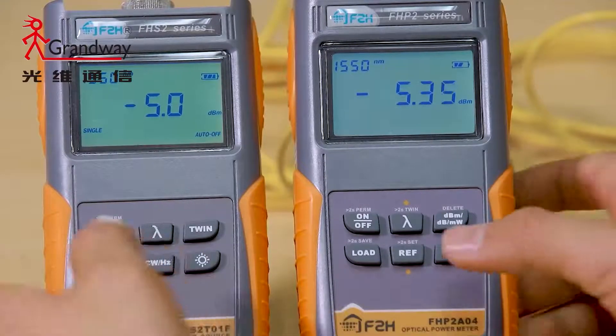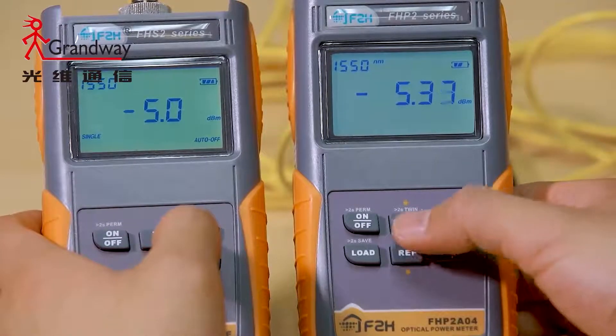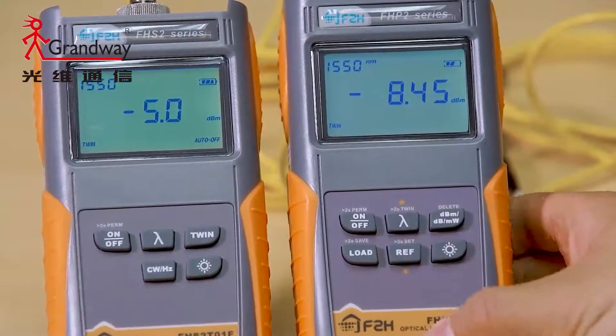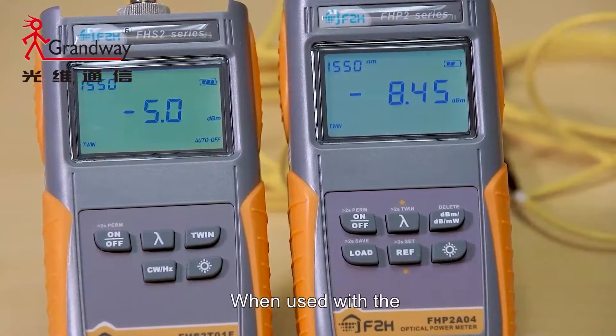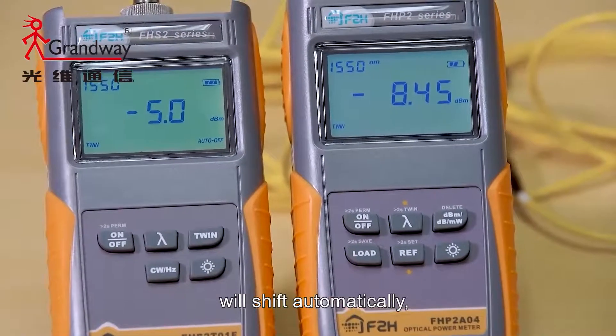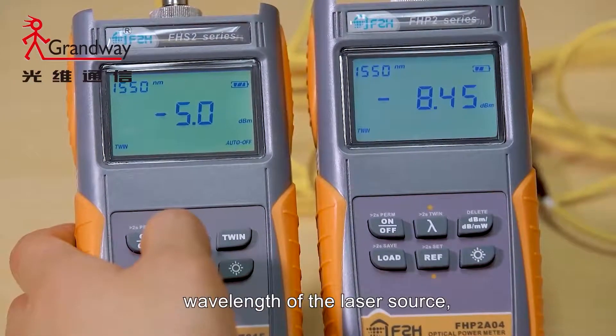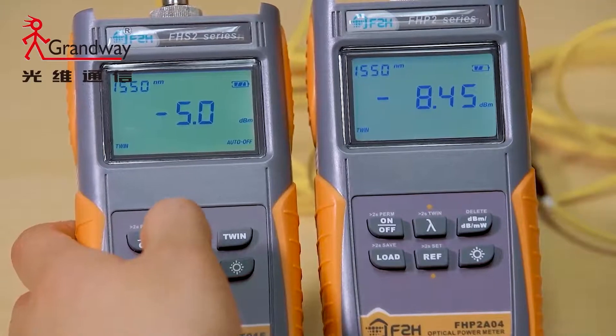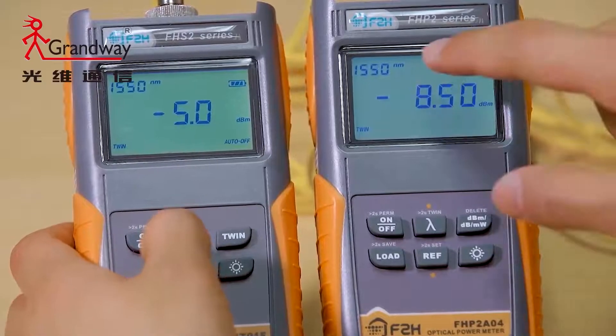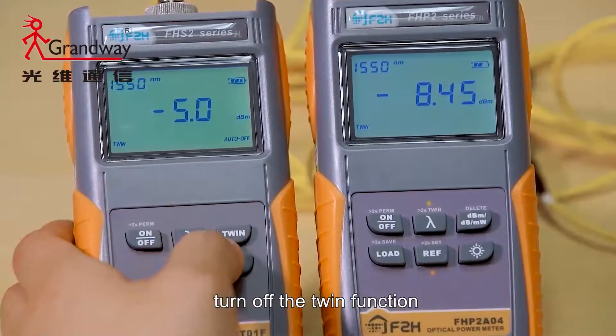Twin function: Turn on the twin function on the laser source and the power meter. When used with the FHS two-series optical laser source, the wavelength will shift automatically according to the output wavelength of the laser source. Turn off the twin function.